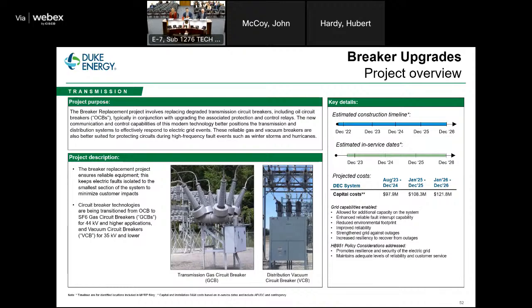For those distribution levels, we replace the legacy oil breaker with a vacuum technology breaker. And then for the high voltage, the current technology is a high pressure gas circuit breaker. But these, combined with our relay upgrades, much more reliably and consistently interrupt those faults and ensure, again, that we're isolating that problem to the smallest portion of the grid. This is important, not just from an outage standpoint, but from availability of generation, especially as we have more distributed energy generation around greater parts of the grid, more circuits being impacted.